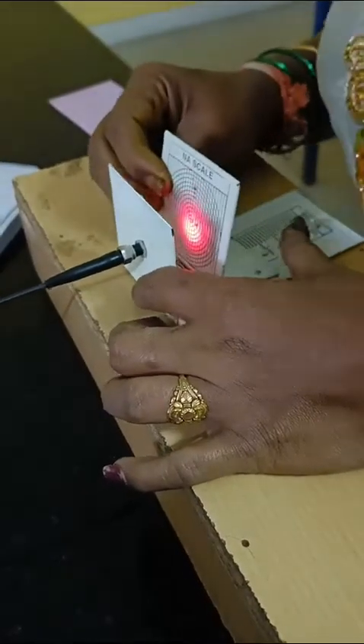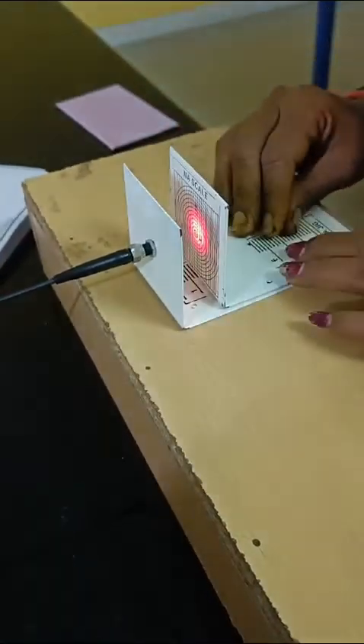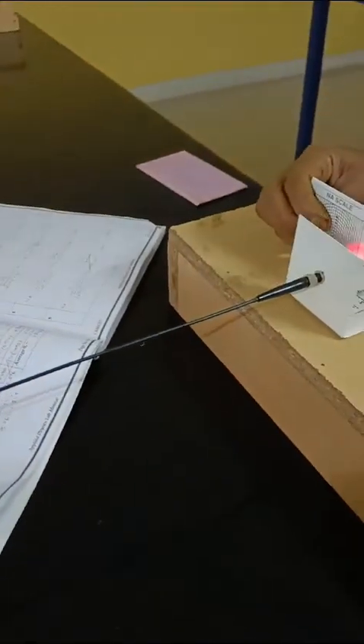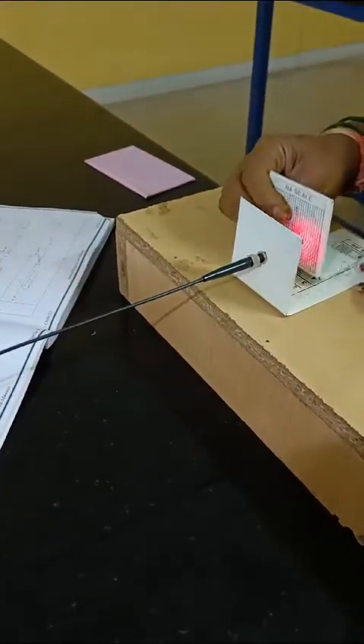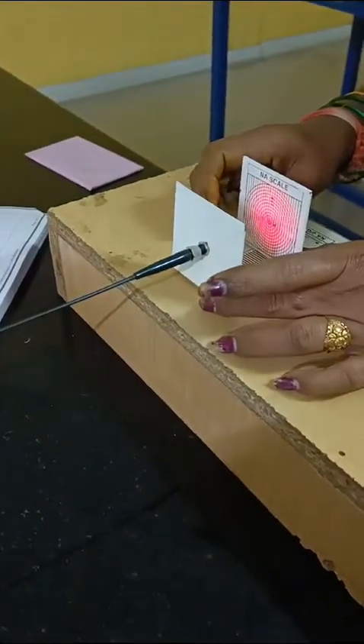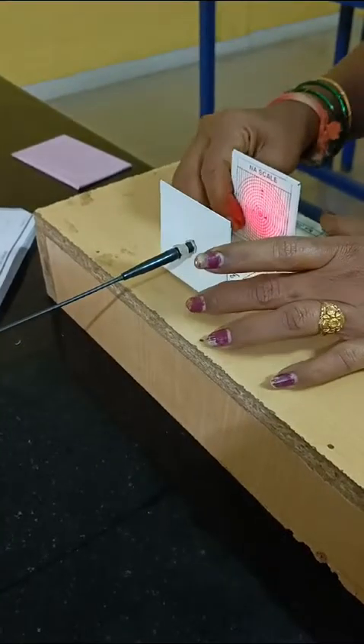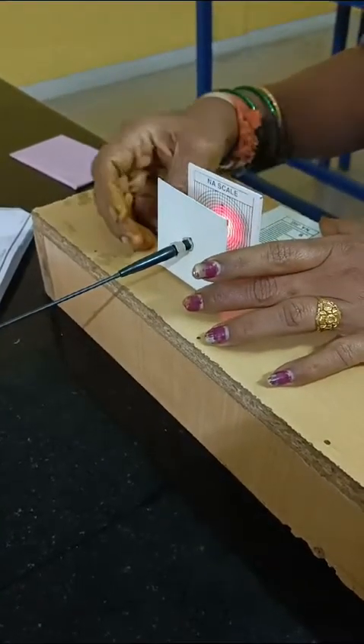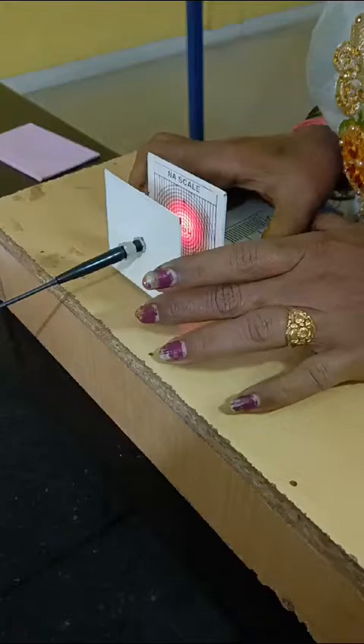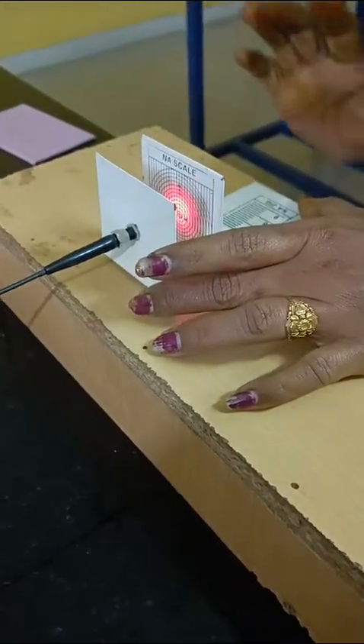There is no hard and fast rule to take only 4mm increments. You can use 5mm, 10mm, 20mm and so on. However, as you move away from the light source, the image becomes unclear on the screen. So we use shorter distances to have clear images and accurately measure the width of the light spot.